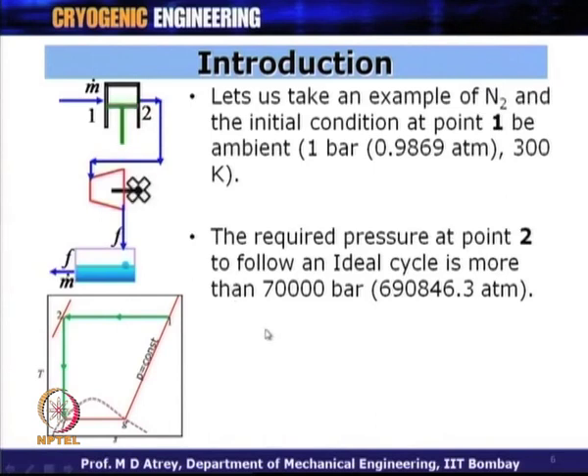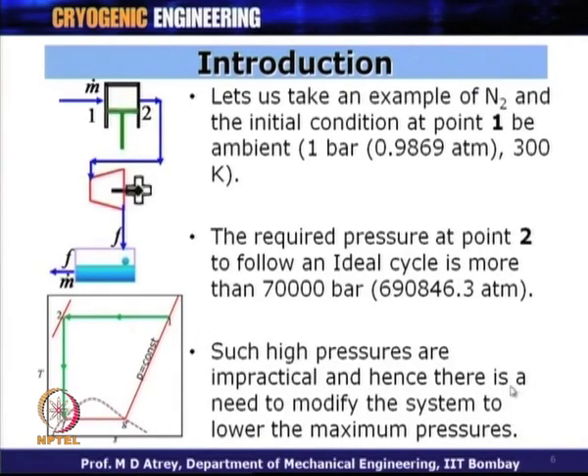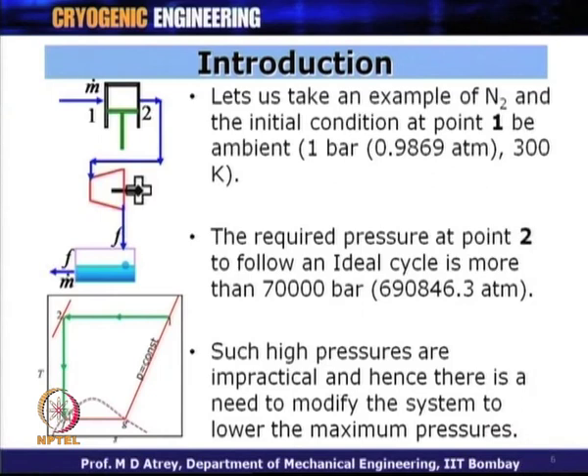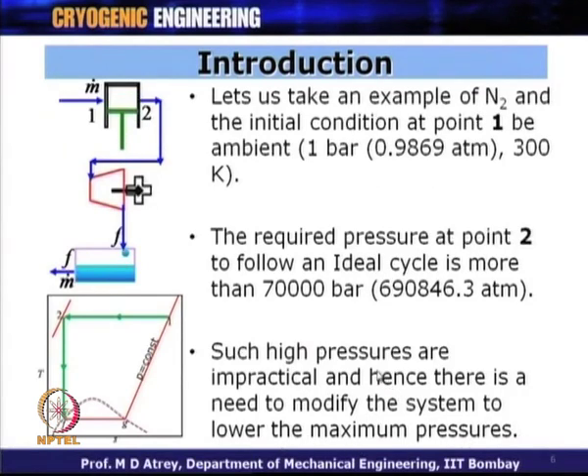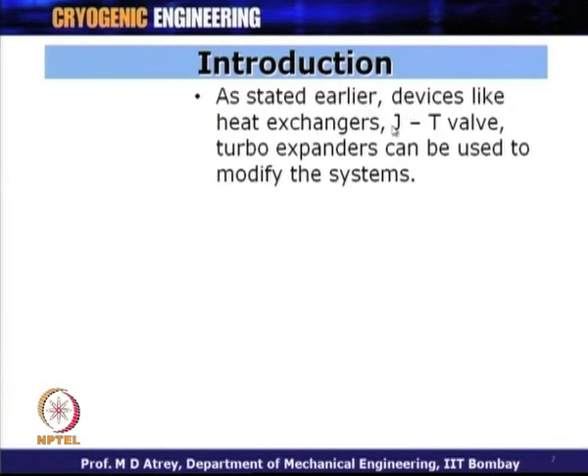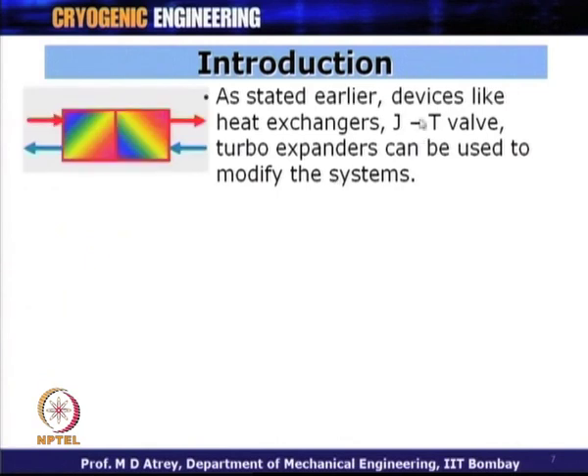What we conclude from here is that such high pressures are impractical, and hence there is a need to modify the system to lower the maximum pressure. The ideal thermodynamic cycle for liquefaction is impractical, and we have to modify it so that we lower the maximum pressures to those normally attainable using available compressors. Devices like heat exchangers, Joule-Thomson valves, and turbo expanders could all be used to modify the system and get a relatively practical cycle.